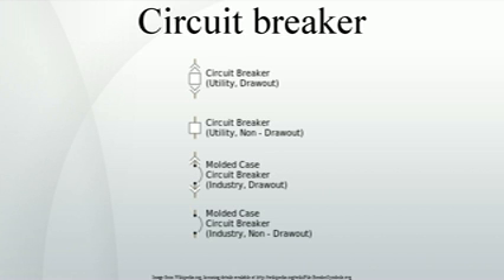Other breakers. The following types are described in separate articles. Breakers for protection against earth faults too small to trip an overcurrent device. Residual current device, RCD, formerly known as a residual current circuit breaker, detects current imbalance, but does not provide overcurrent protection. Residual current breaker with overcurrent protection, RCBO, combines the functions of an RCD and an MCB in one package. In the United States and Canada, panel-mounted devices that combine ground, earth fault detection and overcurrent protection are called ground fault interrupter, GFI, breakers. A wall-mounted outlet device or separately enclosed plug and device providing ground fault detection and interruption only, no overload protection, is called a ground fault circuit interrupter, GFCI.